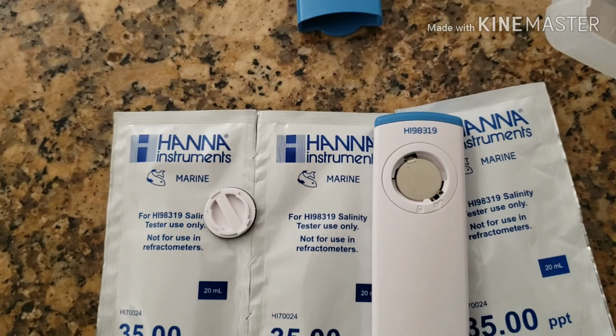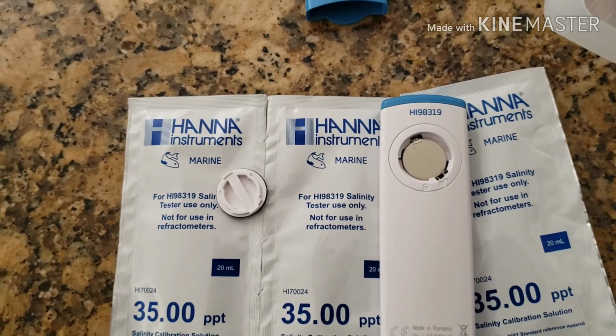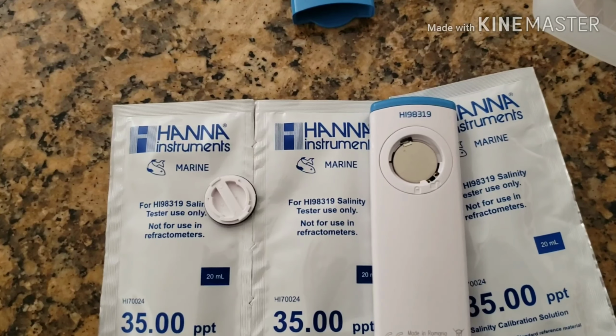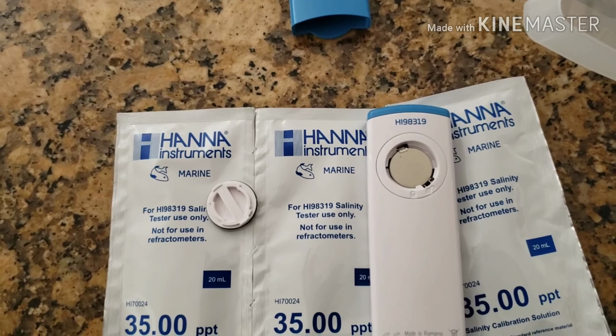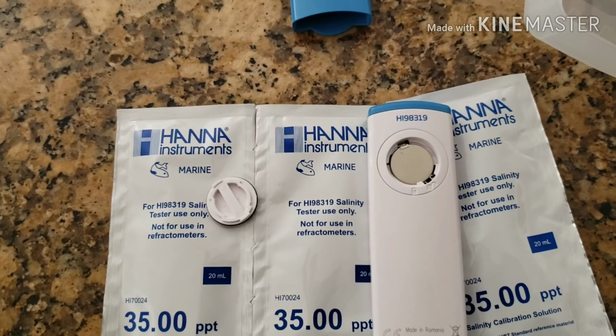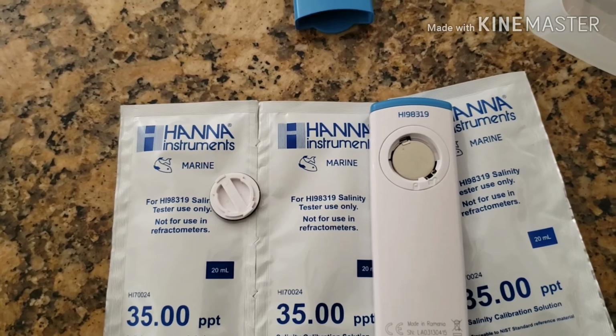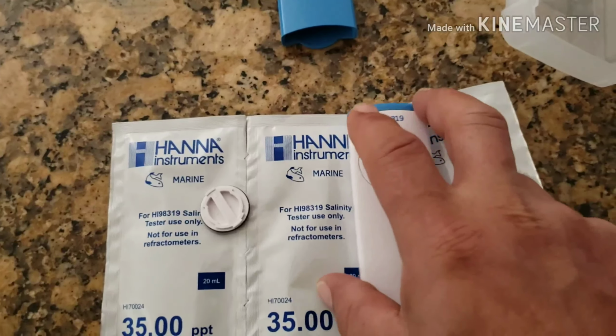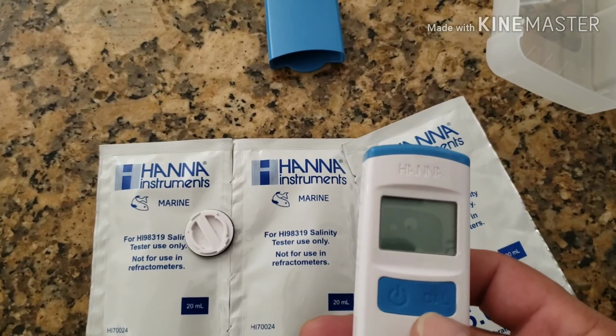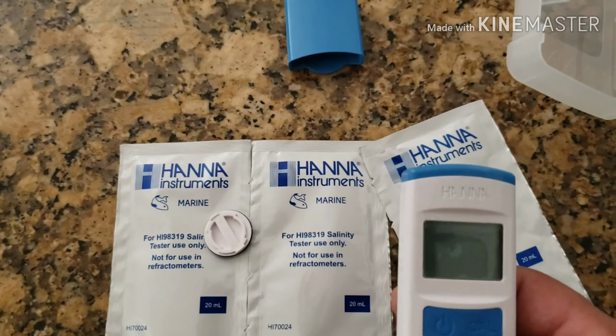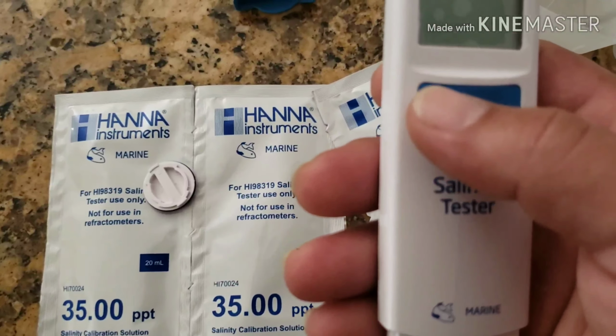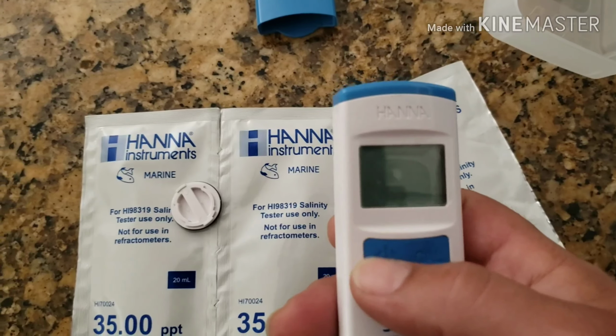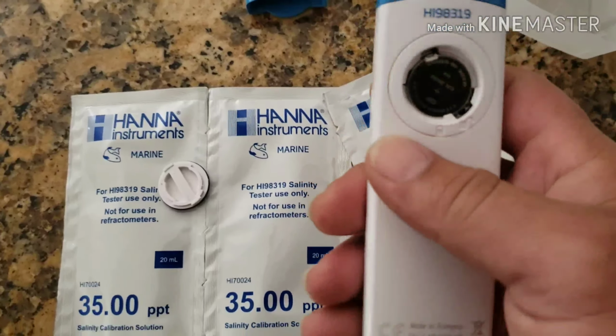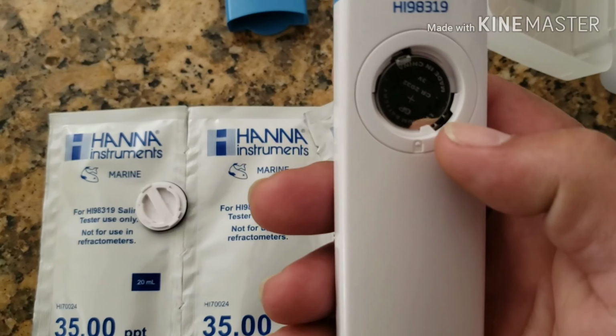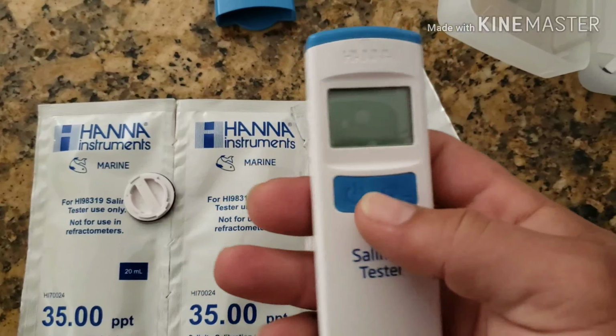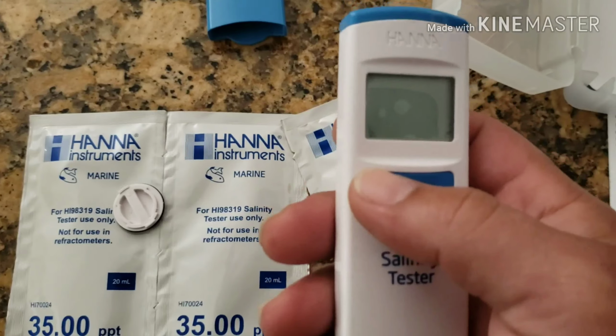So you want to locate that black button, push it, and you will enter the setup mode. Then you want to press the on-off button to move through the setup parameters. So the on-off button would be the power button. So basically you turn the tester on, take the battery compartment off, push in the black button, turn the unit back over. It will display specific gravity.